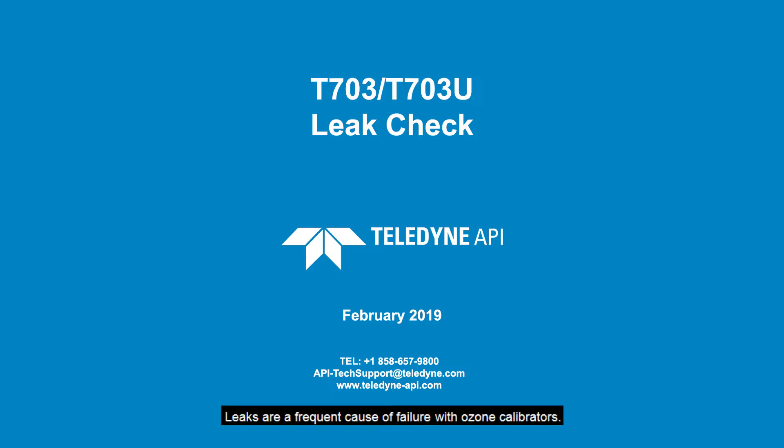Leaks are a frequent cause of failure with ozone calibrators. They can lead to moisture buildup inside the instrument, eventually causing a catastrophic failure.